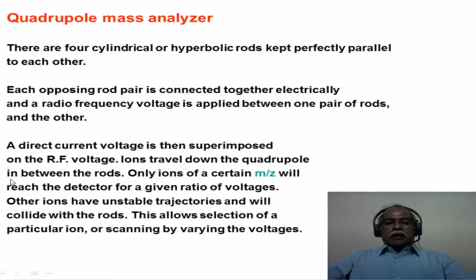A direct current voltage, in other words a DC voltage, is applied and superimposed on a radio frequency voltage. Ions travel down between the quadrupole rods, and in doing so they take a path which looks like a corkscrew. In other words, a helical path is what they take when going through the quadrupolar analyzer. For example, a positively charged ion will come closer to the negatively charged electrode, but by the time it approaches the negatively charged electrode, that electrode will be charged positive because the alternating radio frequency alternates the charges along the electrode, so the ion gets repelled, then comes closer to, let us say, another negatively charged electrode. By the time it comes close here, it will be positively charged. In other words, the potential will change, and in the process the ion will take a helical pathway.